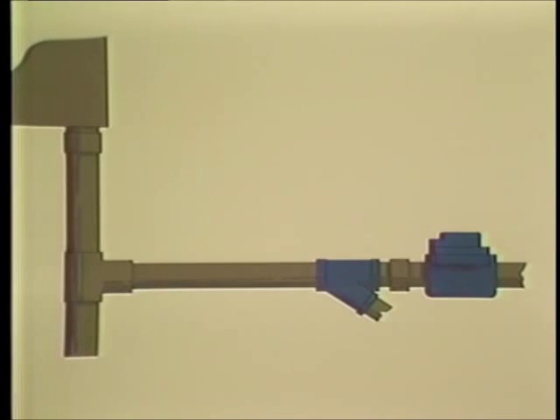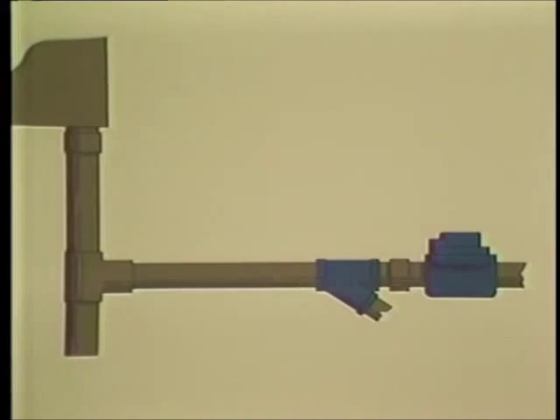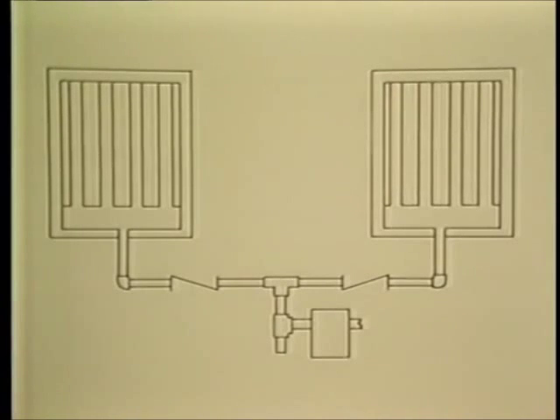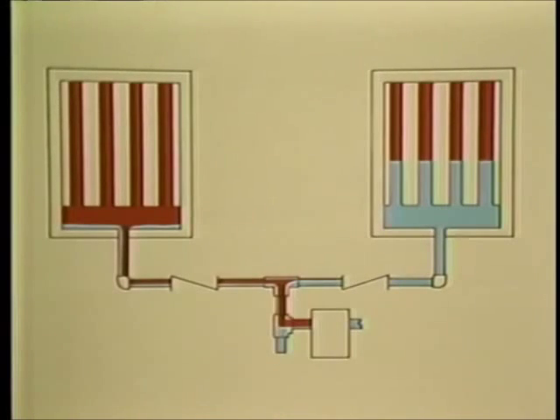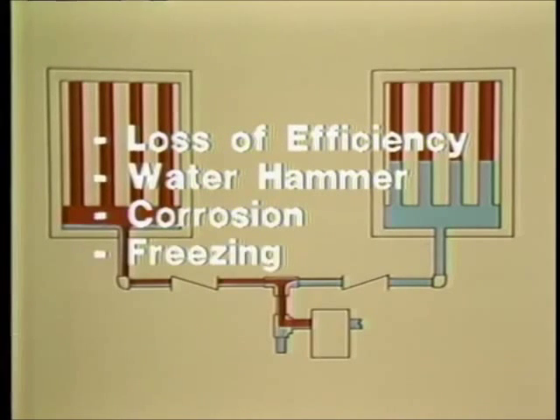Thermostatic and thermodynamic traps should have a longer drip or cooling leg, placing the trap further from the equipment than is recommended for mechanical traps. The reason for this is that thermostatic and thermodynamic traps back up condensate each time the valve closes. Thus, a longer horizontal or vertical drip leg is needed to prevent condensate from backing up into the heat exchanger. Each piece of heat exchange equipment must have its own steam trap. Group trapping — the removal of condensate from several heat exchangers through a single trap — can cause backflow of condensate and air into the heat exchanger with the greatest pressure drop. Even with a check valve to prevent backflow through the trap, condensate can accumulate because steam is still condensing in the heat exchanger. The results of group trapping can be loss of efficiency, water hammer, corrosion, and damage from freezing.